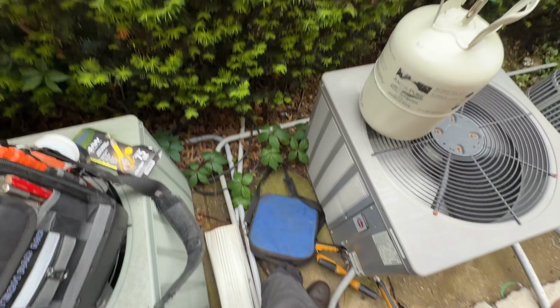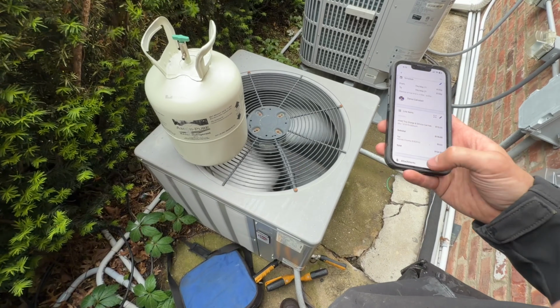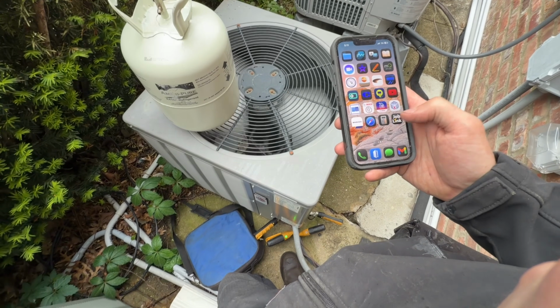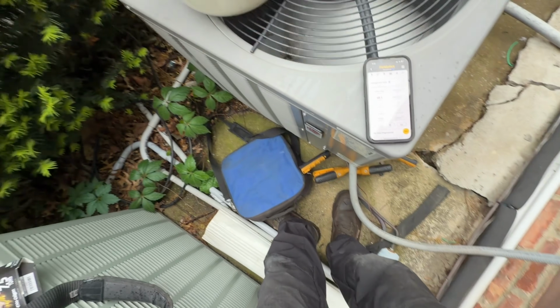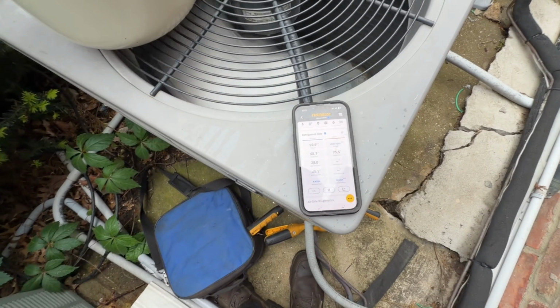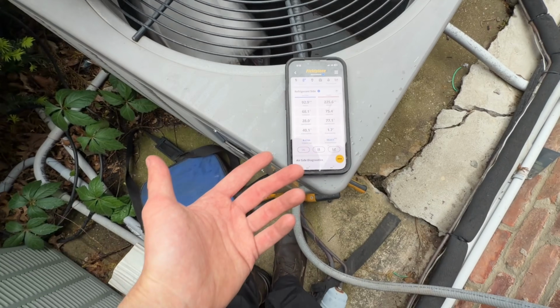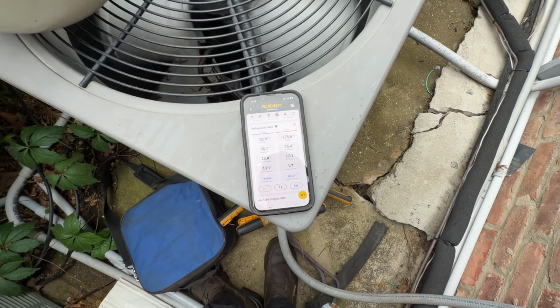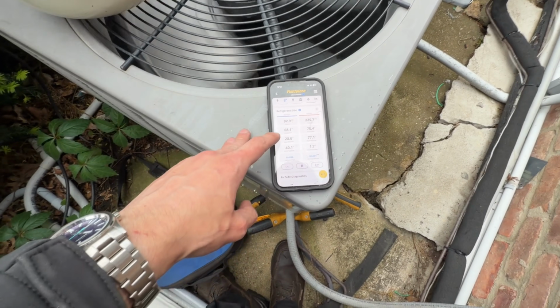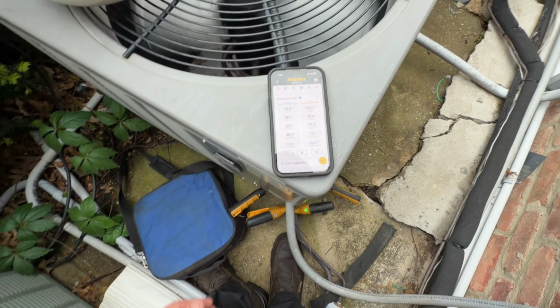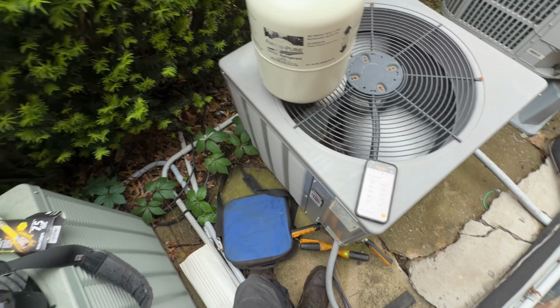So I checked our refrigerant pressures and temperatures. I checked our delta T inside. There is no delta T inside. We got 40 degrees of superheat and 1.7 degrees of subcooling with a low vapor saturation temperature. So this system's low on refrigerant.